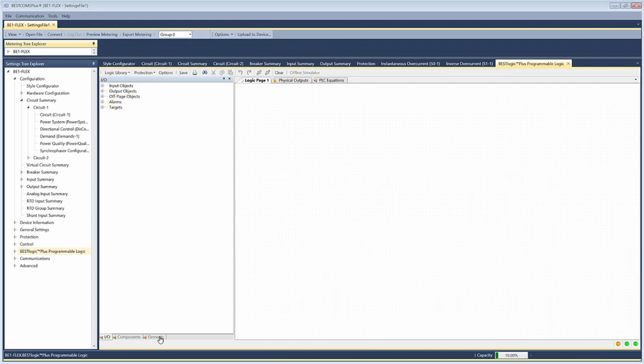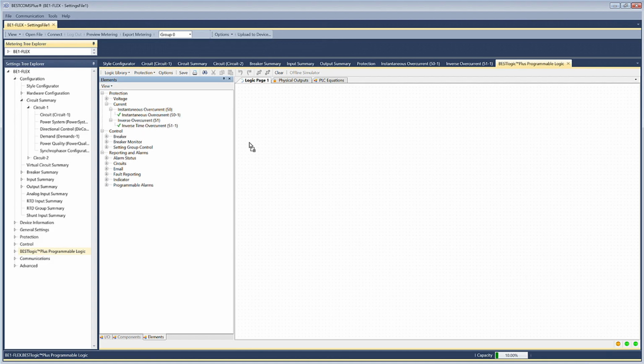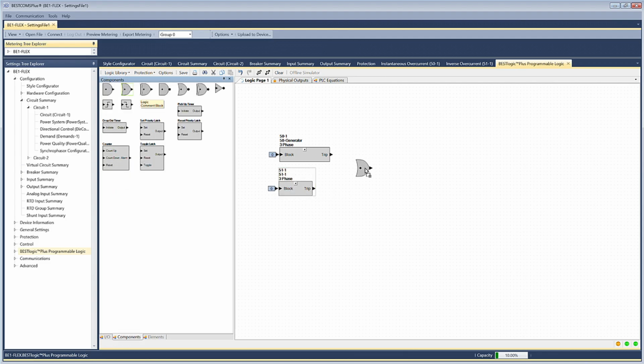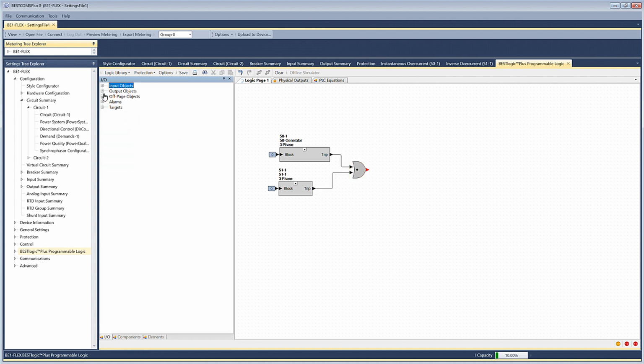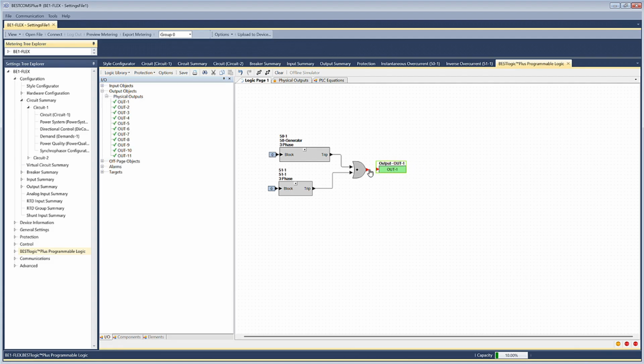I go down into my logic, and now I'm going to actually drive outputs. So I go to my Elements tab, I grab those 2 elements that I had created, I drag them over. I go to my Components tab, I grab an OR gate, because I don't care which one trips. If either one goes to trip, I want to trip that breaker in this particular example. And then I go to my Outputs tab, and I'm just going to use output 1 just for simplicity. And now I've got a happy and healthy logic file.